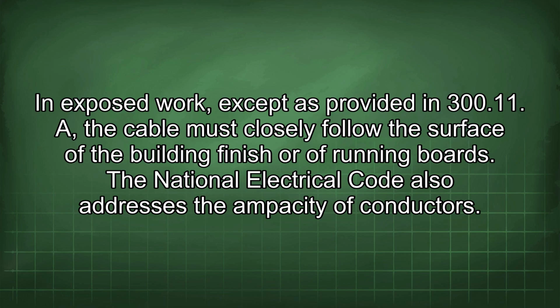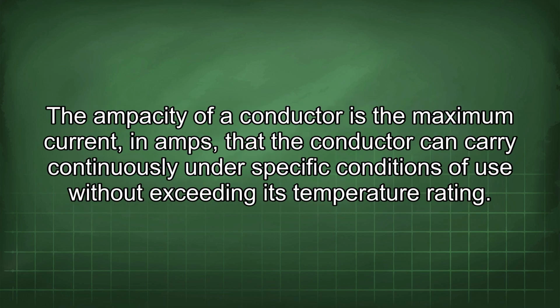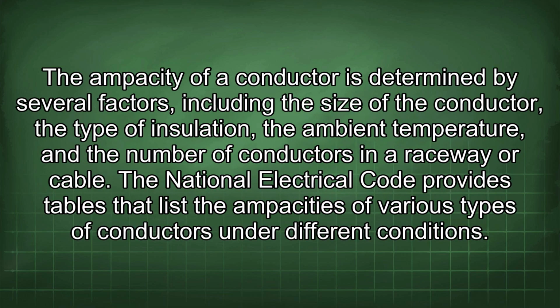The National Electrical Code also addresses the ampacity of conductors. The ampacity of a conductor is the maximum current, in amps, that the conductor can carry continuously under specific conditions of use without exceeding its temperature rating. The ampacity of a conductor is determined by several factors, including the size of the conductor, the type of insulation, the ambient temperature, and the number of conductors in a raceway or cable.